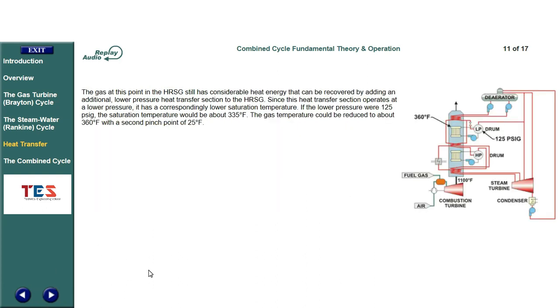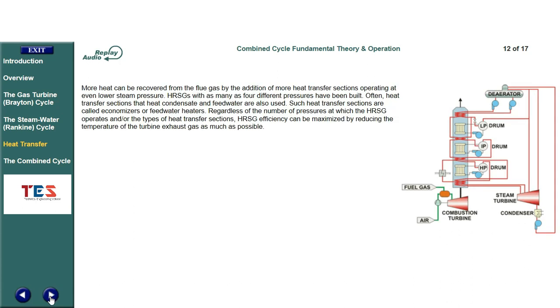The gas at this point in the HRSG still has considerable heat energy that can be recovered by adding an additional lower pressure heat transfer section. Since this section operates at a lower pressure, it has a correspondingly lower saturation temperature. If the lower pressure were 125 PSIG, the saturation temperature would be about 335 degrees Fahrenheit, and the gas temperature could be reduced to about 360 degrees Fahrenheit with a second pinch point of 25 degrees Fahrenheit. More heat can be recovered by adding more heat transfer sections at even lower steam pressures. HRSGs with as many as four different pressures have been built. Heat transfer sections that heat condensate and feed water, called economizers or feed water heaters, are also commonly used.